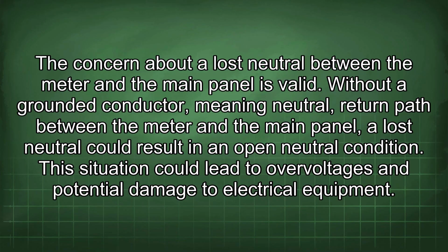The concern about a lost neutral between the meter and the main panel is valid. Without a grounded conductor, meaning neutral, return path between the meter and the main panel, a lost neutral could result in an open neutral condition. This situation could lead to overvoltages and potential damage to electrical equipment.